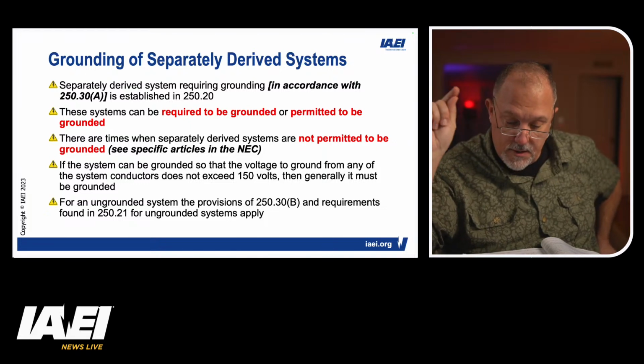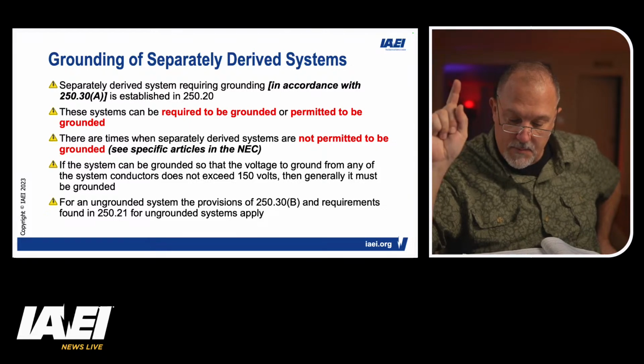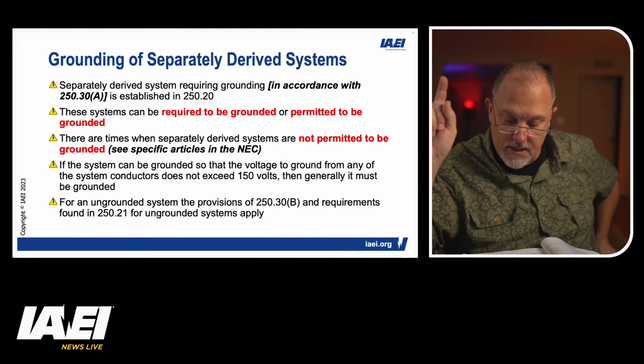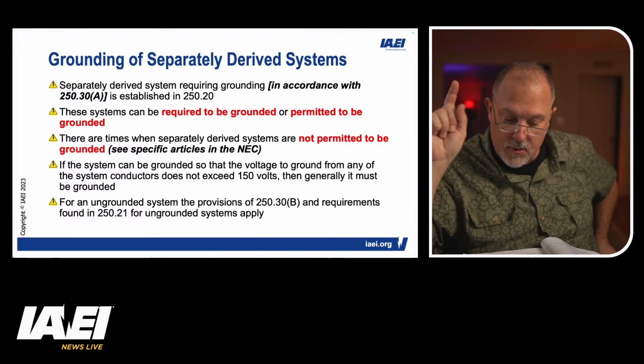Multiple power sources of the same type that are connected in parallel to form one system that supplies premises wiring shall be treated as a single separately derived system and shall be installed in accordance with 250.30.